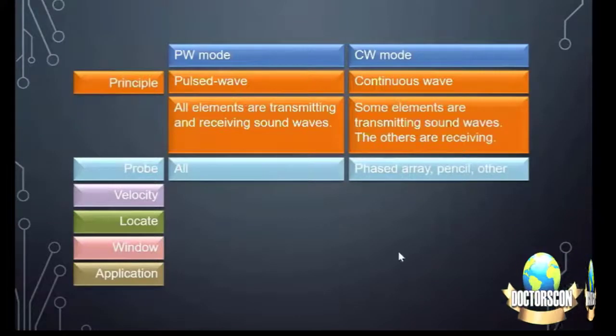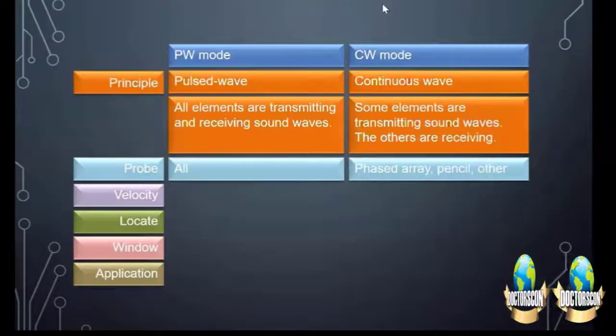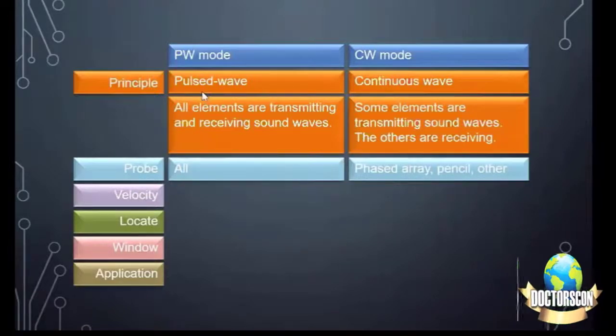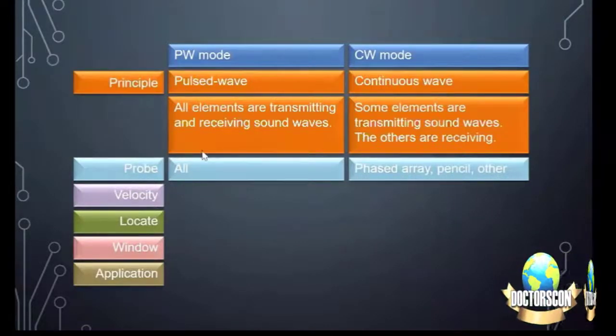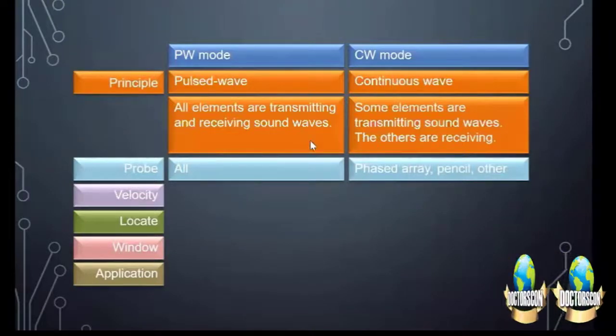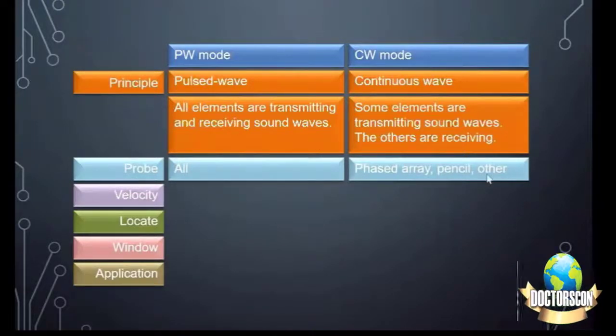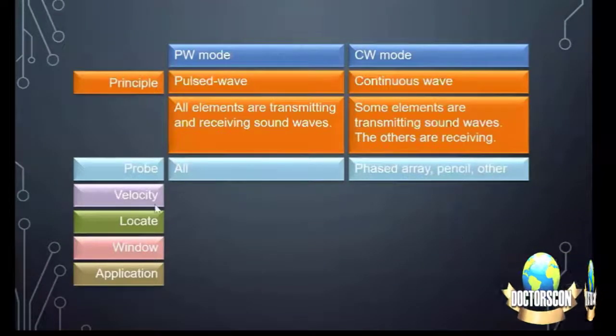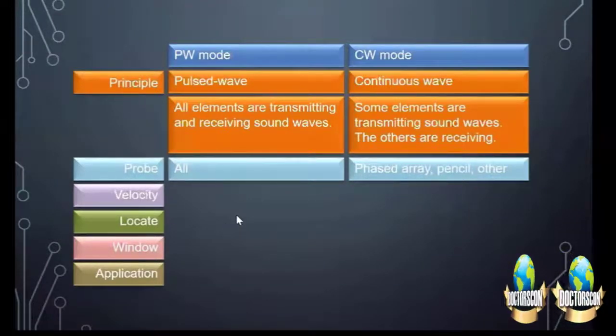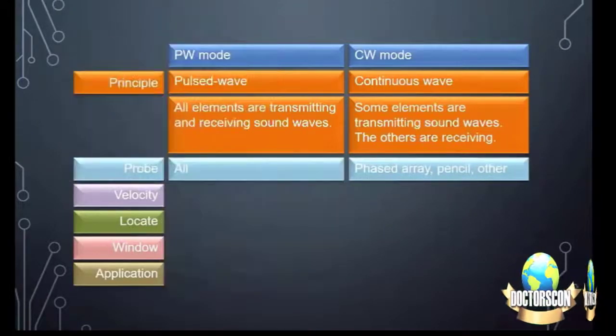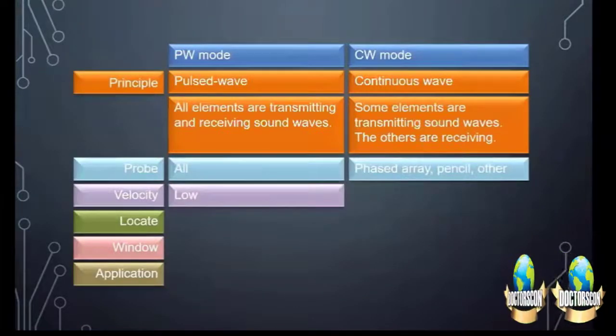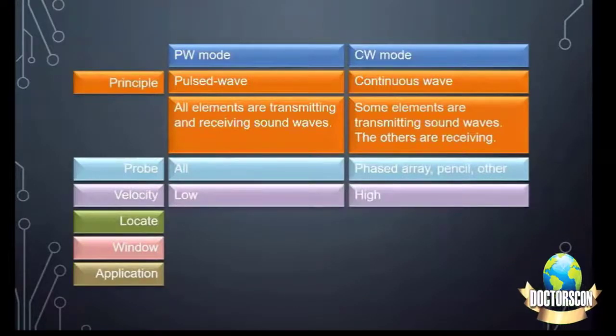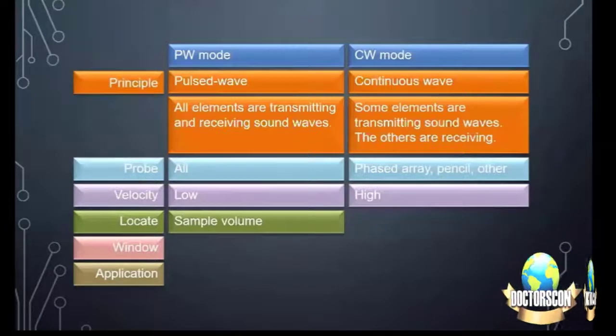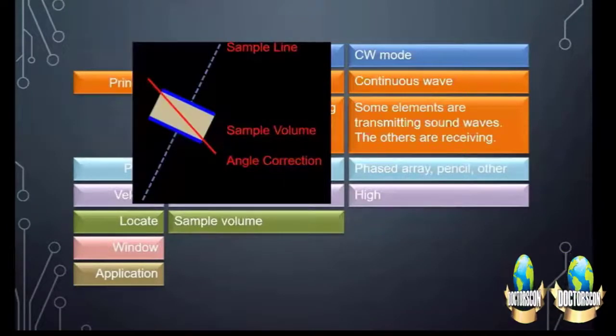The difference between pulse wave Doppler and continuous wave Doppler is that in continuous wave, some elements are transmitting sound waves and others are receiving. All probes can be used for pulse wave, whereas phased array or pencil probes are used for continuous wave. The velocity measured is low in pulse wave, whereas it is high in continuous wave. A sample volume is required to locate. This is the sample volume here.